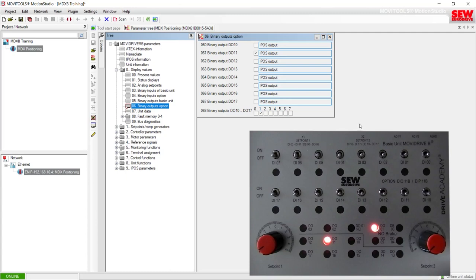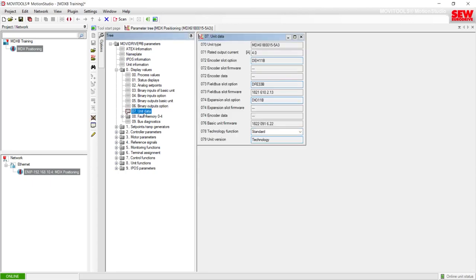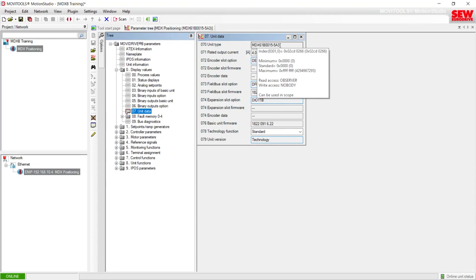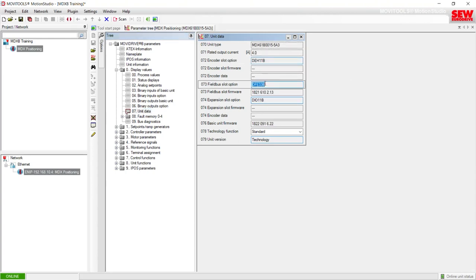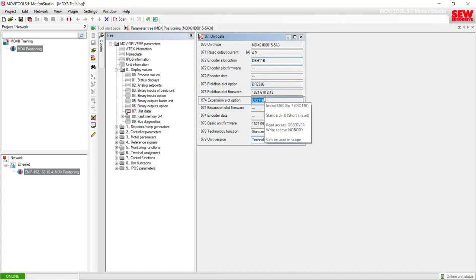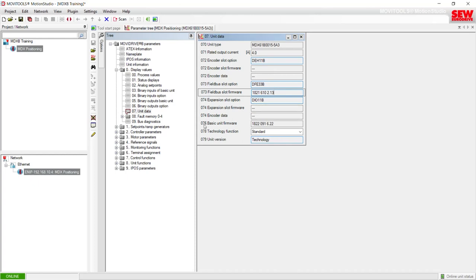The next question in the lab instructions asks about the Unit Data item. Let's go to number seven, Unit Data. Here we can see the model type of our MOVIDRIVE and a list of each one of the option cards installed. To find the firmware of your MOVIDRIVE, look down to parameter 76, which is the basic unit firmware — don't look at the field bus firmware because that's not the same firmware number.